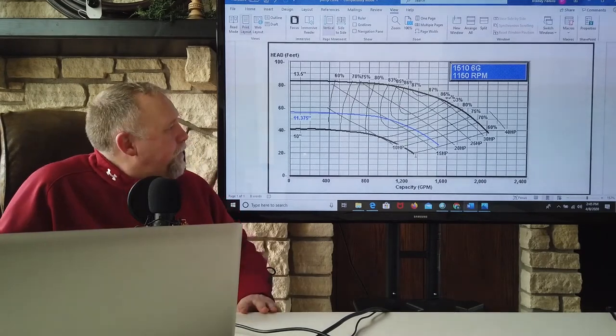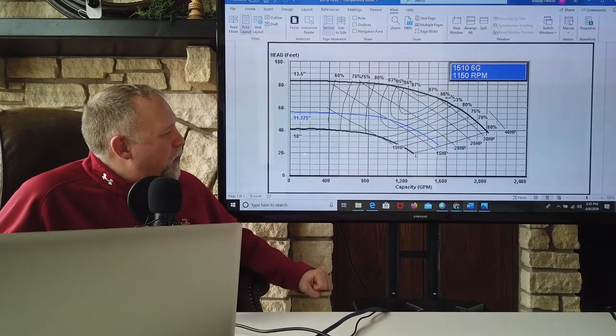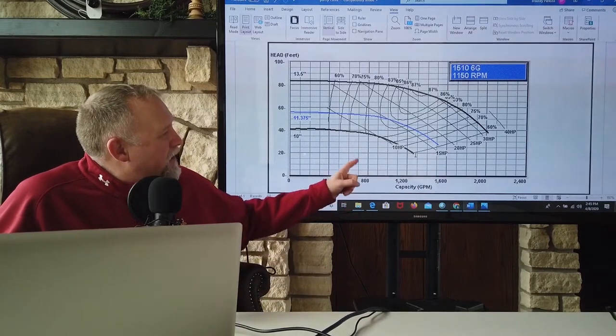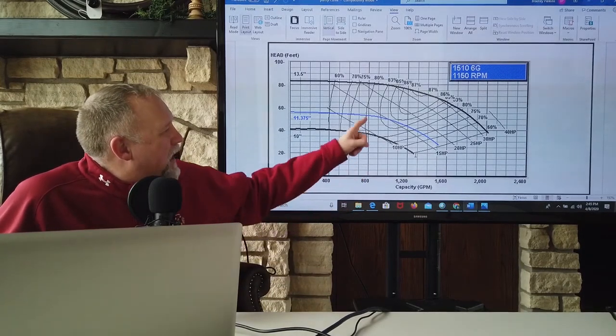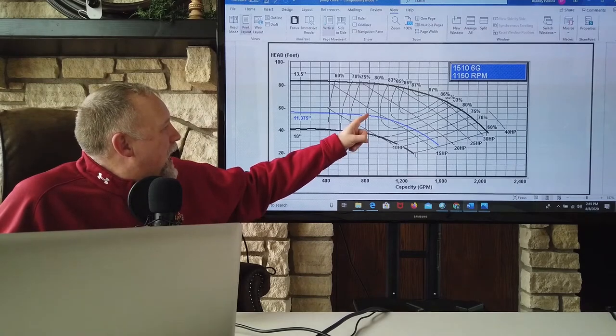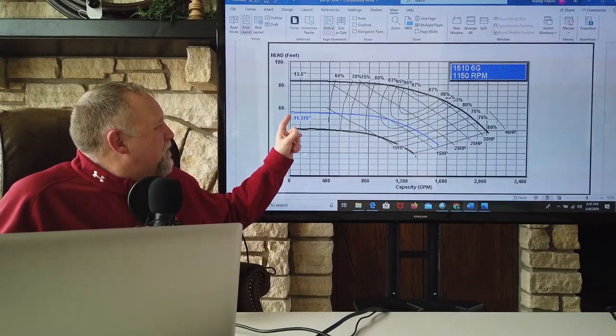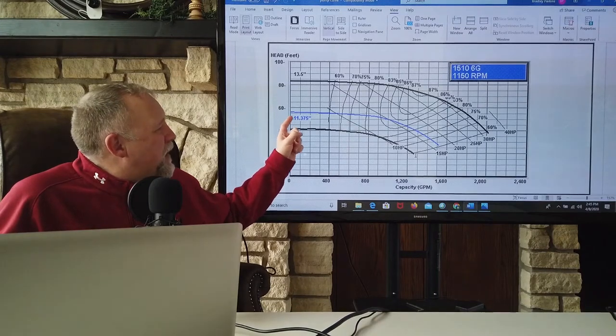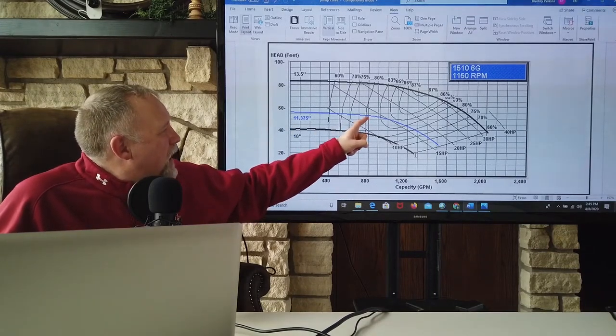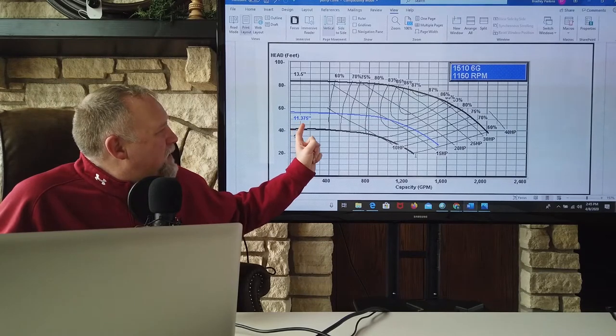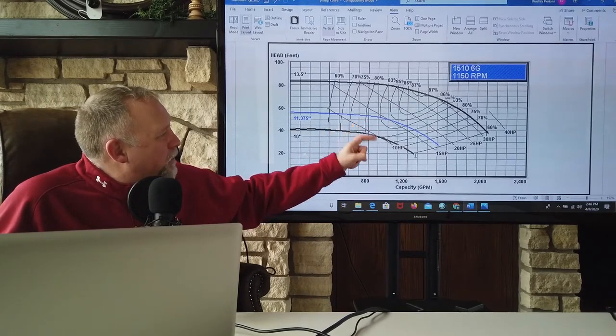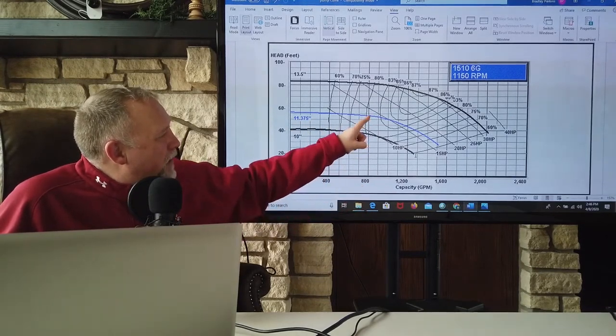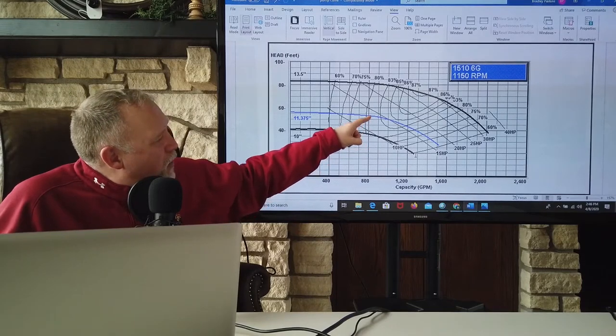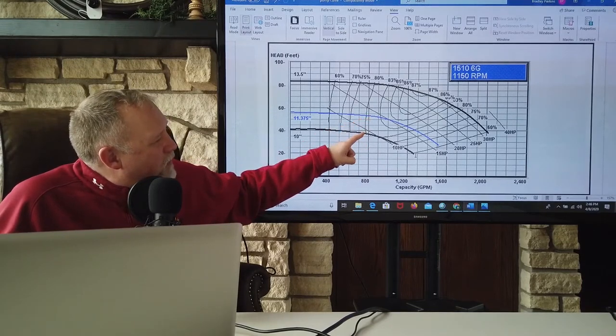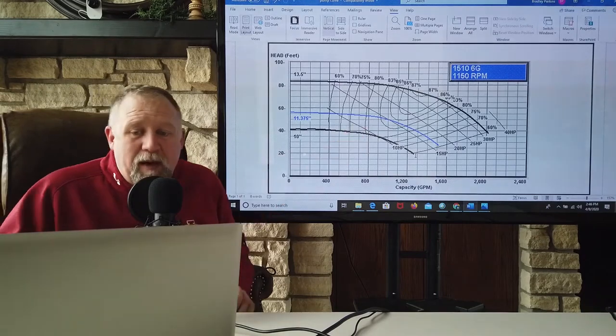See this one? Let's say this pump was operating at 800 gallons a minute and about 53 feet or so of head at an 11.375 inch impeller. We'd be operating right about this point. Notice we'd be between the 10 horsepower line and the 15 horsepower line.